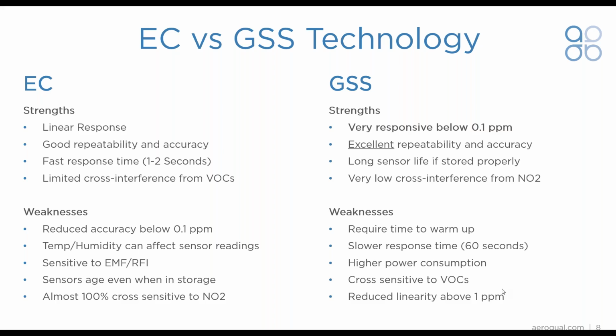What are the differences between them? How do they compare? If you narrow it down in the short term, EC sensors are less affected by VOC cross interference than GSS sensors. They have a fast response time, but they are also 100% cross sensitive to gases such as nitrogen dioxide and chlorine, and they can also be influenced by temperature and humidity changes. On the other side, we have GSS sensors, which are very responsive to ozone below 0.1 ppm. They have excellent repeatability and accuracy versus the good repeatability and accuracy of an EC sensor, but they are cross-sensitive to the presence of volatile organic compounds, and they do have a slower response time.